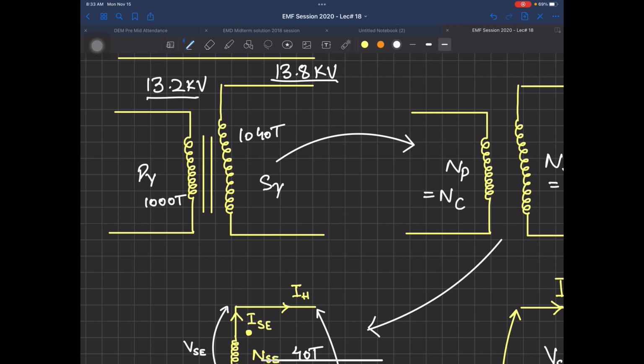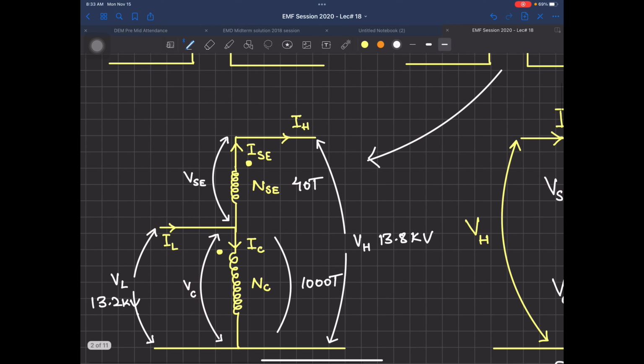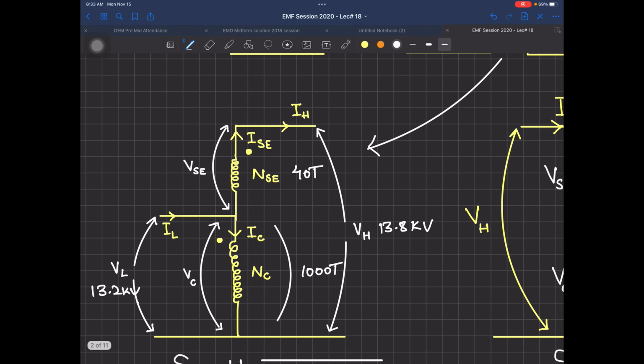Because now on the secondary side you don't require another 1000 turns, but just connect the windings in series, which means this is the common winding and this is your series winding, and the dot convention is still being followed.